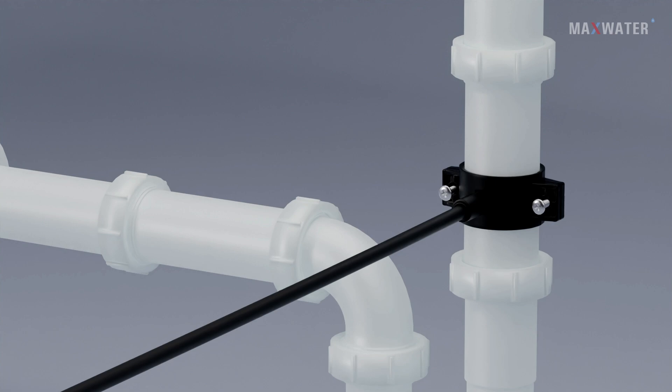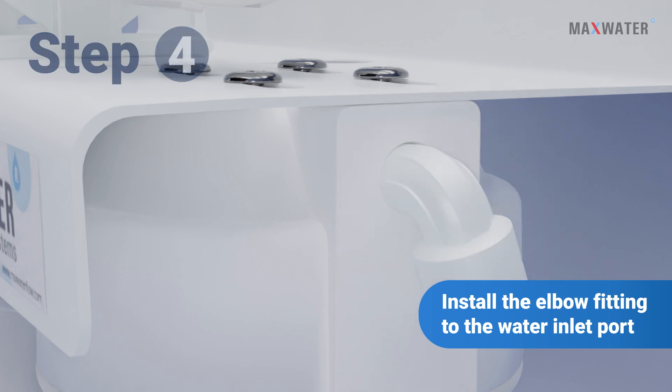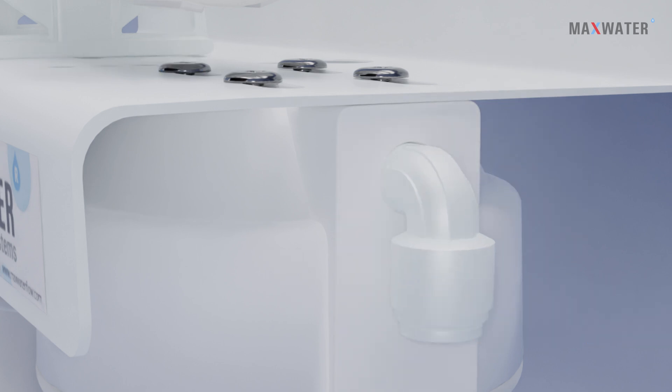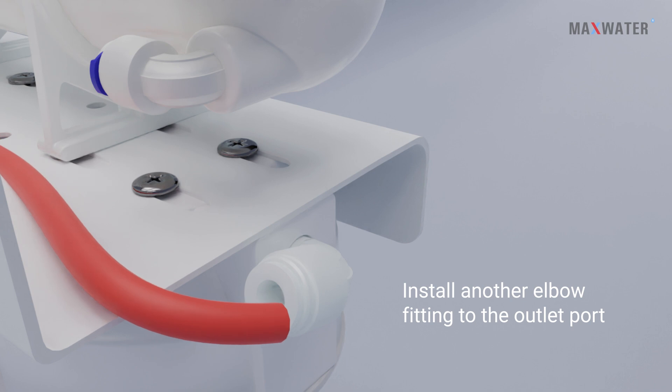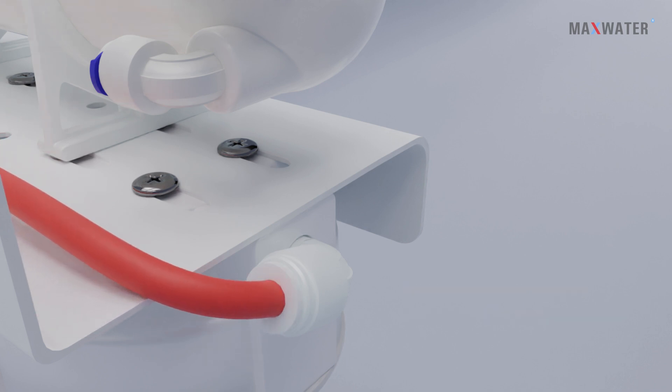Step four: install the elbow fitting to the system water inlet port, then connect the red tubing from the feed water adapter through the elbow fitting. Now on the opposite side of the system, install another elbow fitting to the outlet port, but connect the red tubing from the auto shut-off valve's inlet to the elbow fitting. Do not over tighten any of those fittings.